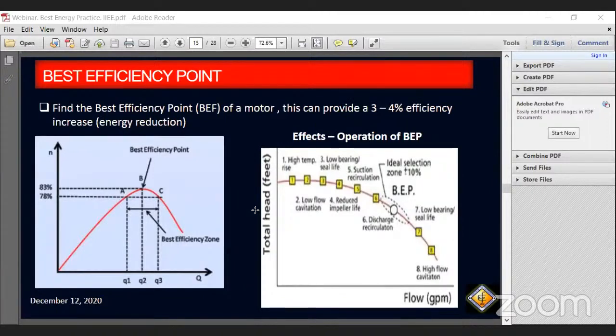The right graph shows the effect of operating away from the best efficiency point. If you go to the left side, higher head, you'll get high temperature rise, low bearing seal life, suction recirculation, reduced impeller life, and low flow cavitation. If you go to low head, high flow, you'll get low bearing seal life. So just find the best efficiency point.